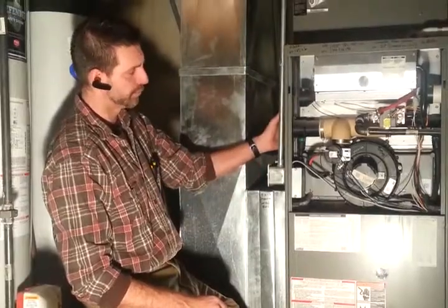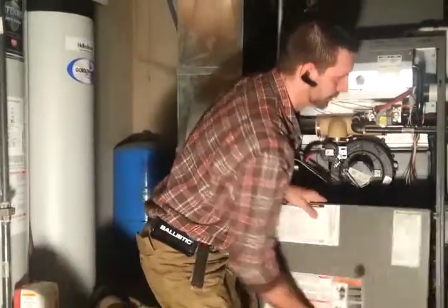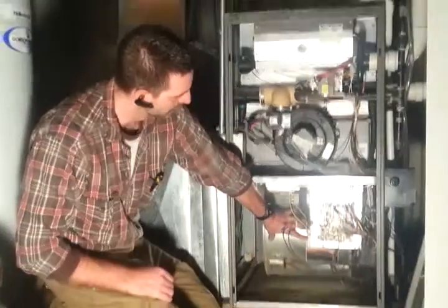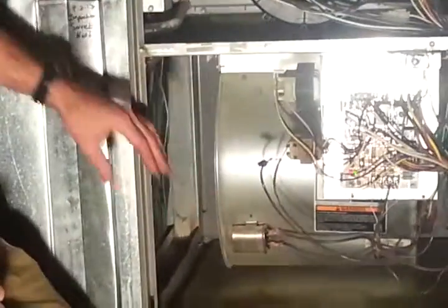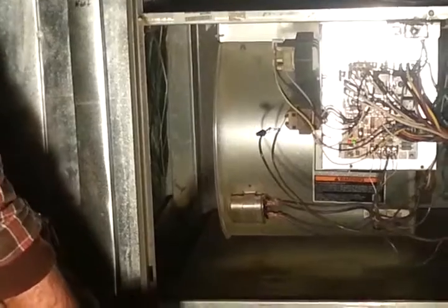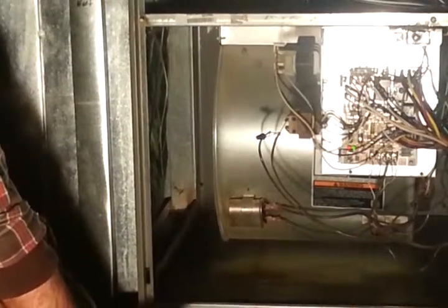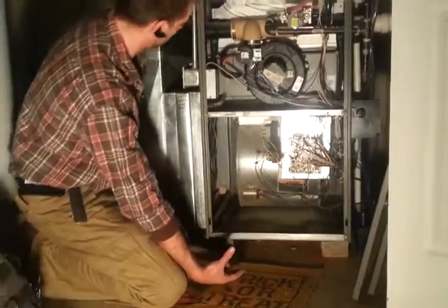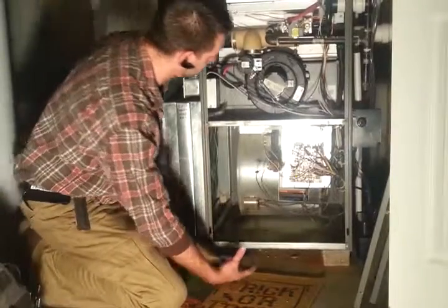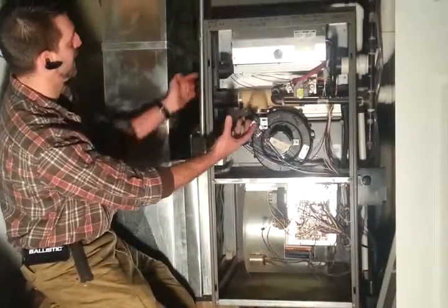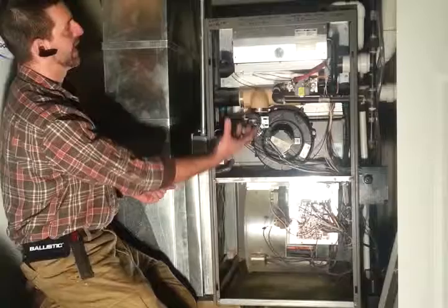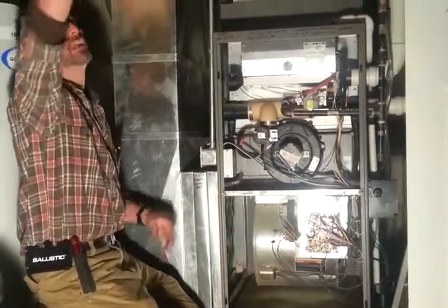So a heat exchanger is very important. And then underneath here, again, I've got my safety switch taped off. This is my blower. So the blower motor, because I have a forced air furnace, an upright furnace, so I'm taking the air from my return air duct, taking it and blowing it up against my heat exchanger, making that air nice and hot, taking it up and out.